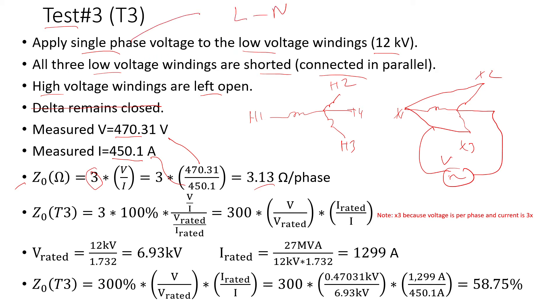This result is 3.13 ohms per phase. The current that flows in the windings is three times the per-phase winding current. So the total measured current is three times the per-winding current. Those threes cancel, leaving per-phase voltage and per-phase current, giving the zero sequence impedance per phase.